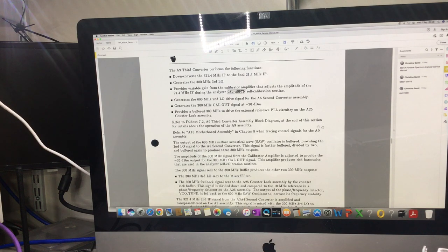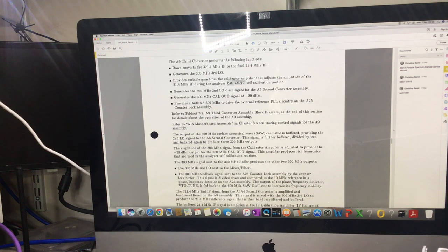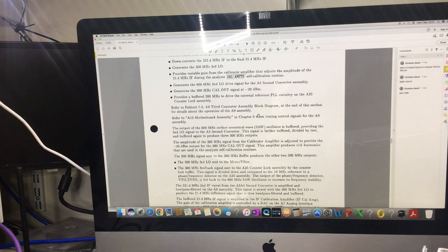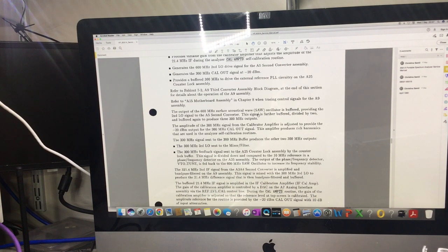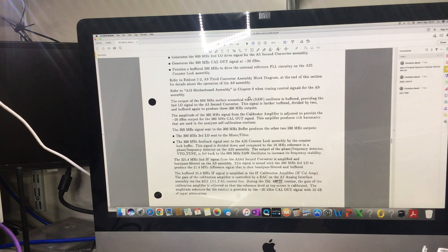Okay, the third converter performs the following. Down converts 321.4 MHz to 21.4 IF. Generates a 300 MHz third local oscillator. Provides variable gain of a calibration amplifier, which we went through earlier in the video, if you remember. Generates 600 MHz second local oscillator drive signal for the A5 second converter assembly. Generates 300 MHz cal out signal at minus 20 dBm. Provides a buffered 300 MHz to drive the external reference PLL circuitry on A25 counter lock. Refer to foldout 7-2, A9 third converter assembly block diagram at the end of this section. Details of operation of the A9 assembly.